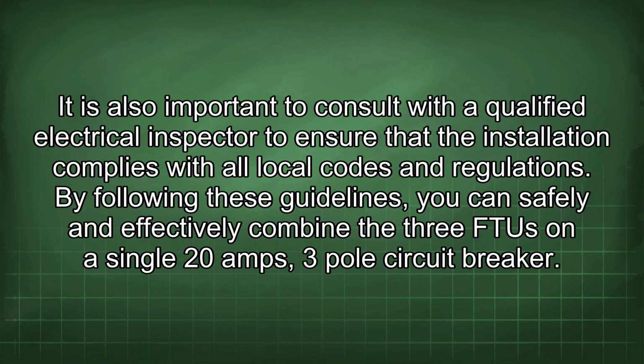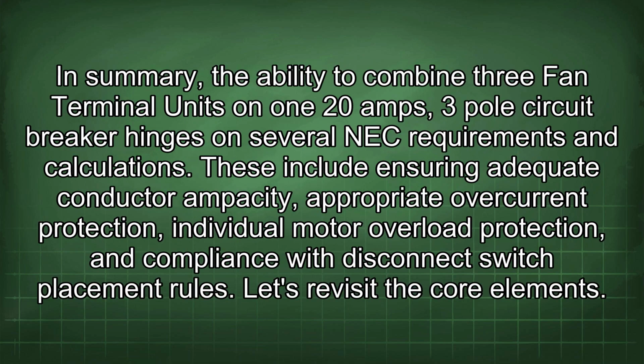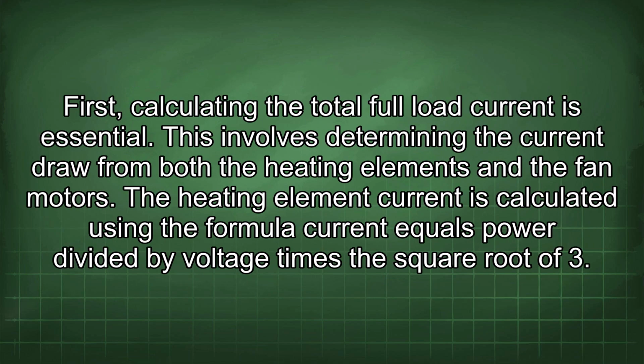In summary, the ability to combine 3 fan terminal units on one 20 amp 3-pole circuit breaker hinges on several NEC requirements and calculations. These include ensuring adequate conductor ampacity, appropriate overcurrent protection, individual motor overload protection, and compliance with disconnect switch placement rules. Let's revisit the core elements. First, calculating the total full load current is essential. This involves determining the current draw from both the heating elements and the fan motors.